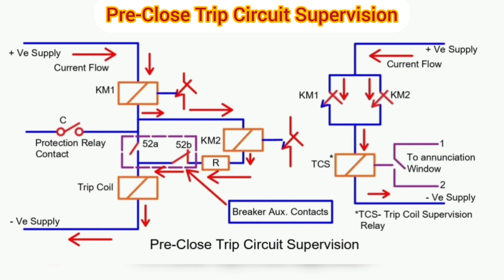If both KM1 and KM2 relays do not operate, the TCS relay will not operate and the contact of TCS will remain in the NC state. The annunciation window will glow in this case, indicating that either the supply is missing, the trip coil is open, or there is a defect in the wiring of the trip circuit supervision circuit.